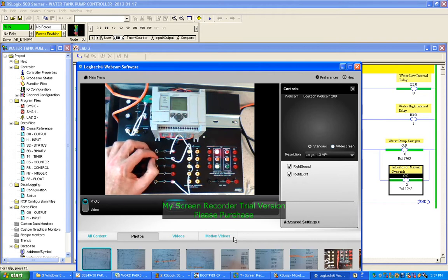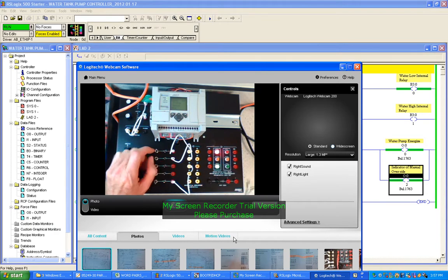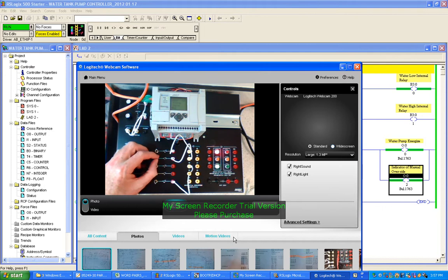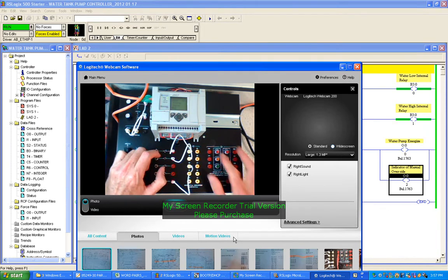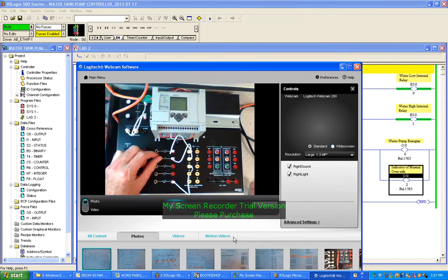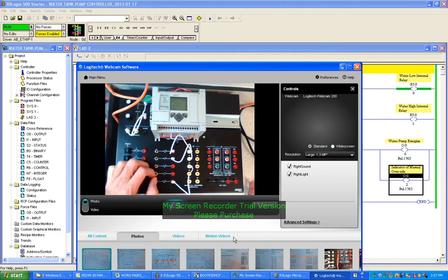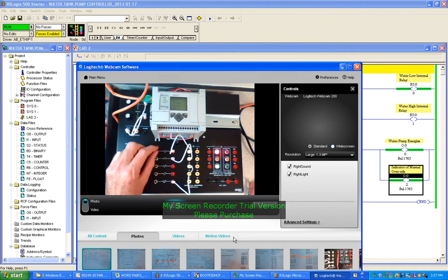Motor on. The first switch indicates the water is too low, so that's turning on and the pump is running. When that hits the full level, the full switch will switch on and the motor turns off - which is sort of what we expected. With the motor running, the motor override switches off. So it seems to be working.